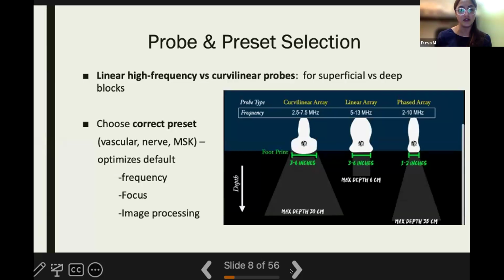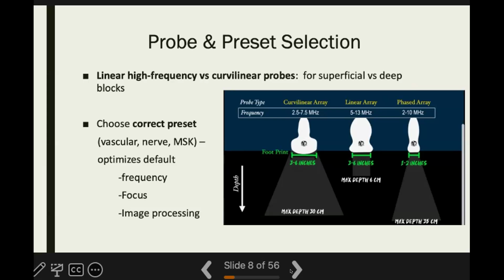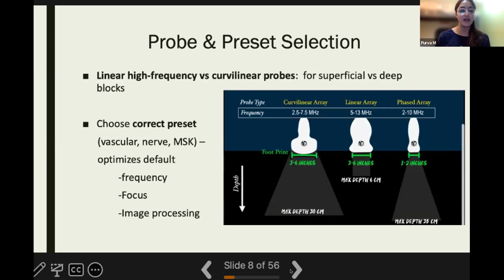So once we have decided what nerve block we wish to perform, and we have selected our probe, which is the curvilinear or linear, we will then select the correct preset, whether we want to scan for a nerve, for any musculoskeletal area of interest, or the vascular.